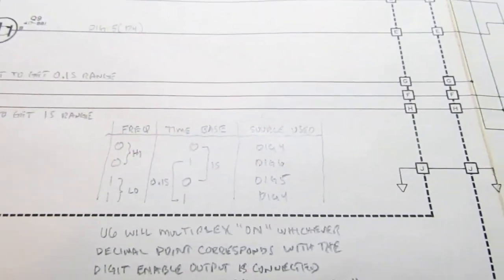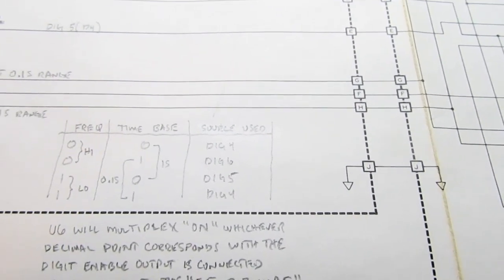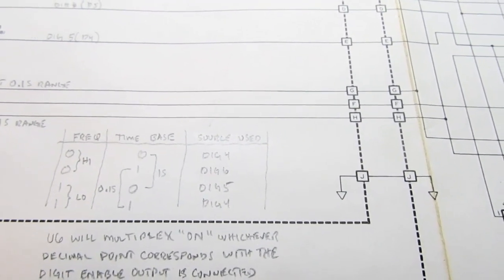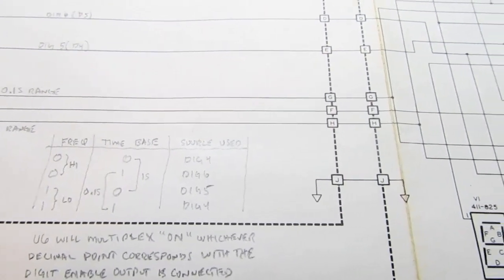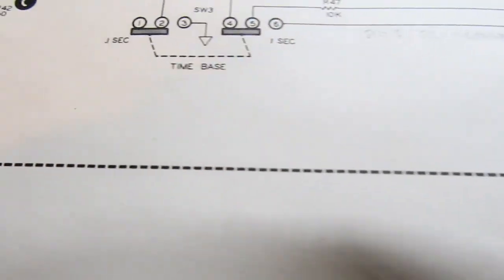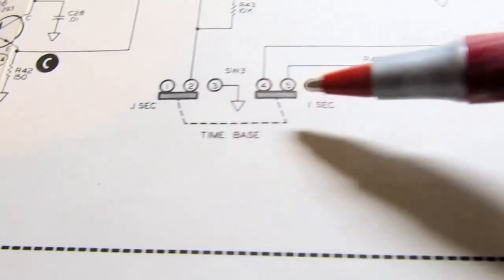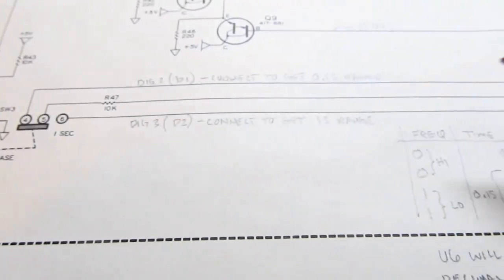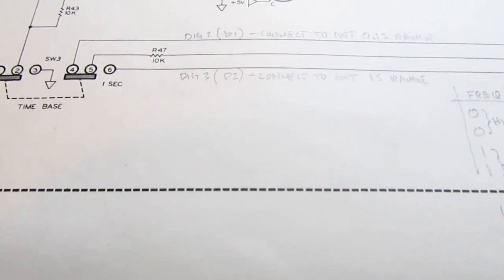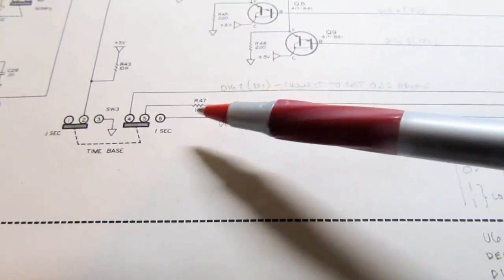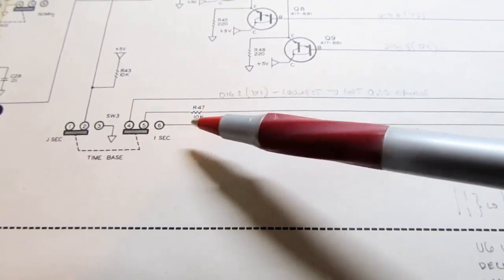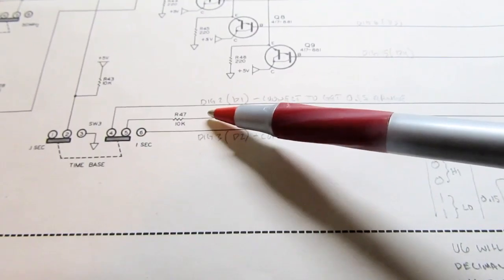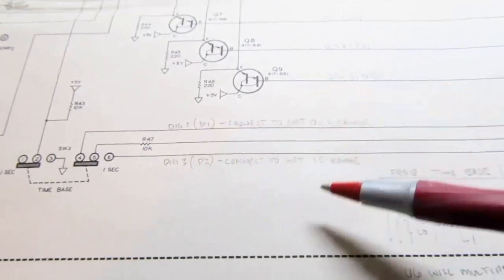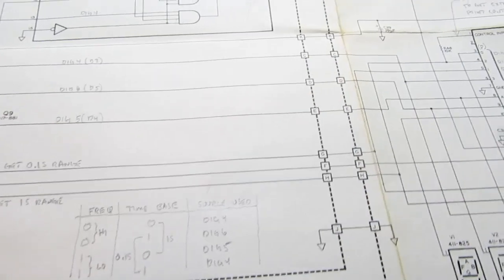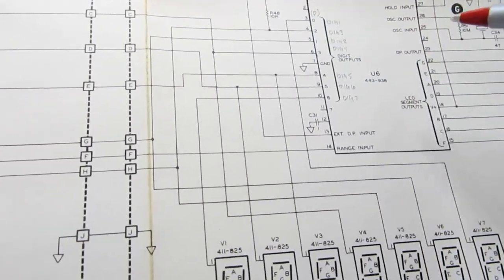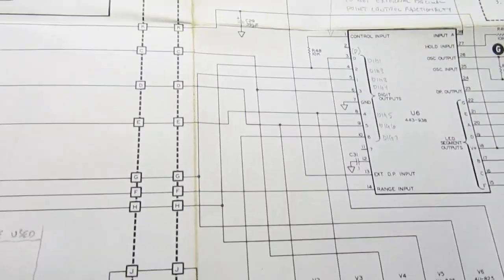It can actually run in 4 different time bases—I think it's 0.01 seconds, 0.1 second, 1 second, or 10 seconds. Because the switch here is limited to just 0.1 second or 1 second, we're only using 2 of the possibilities. But in theory we could put in a bigger switch and connect the range input to 2 additional digit outputs to get even more time bases. It's certainly capable of doing so.